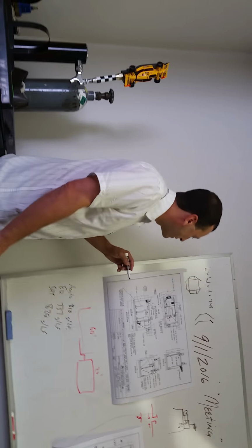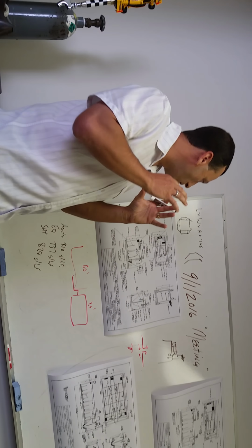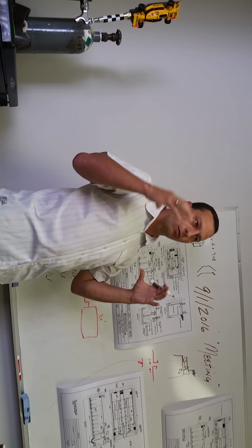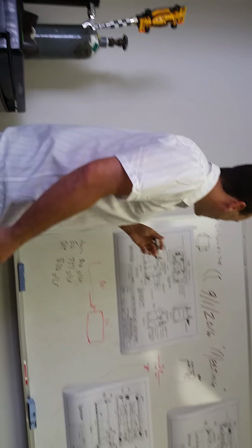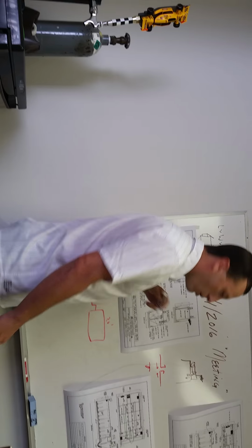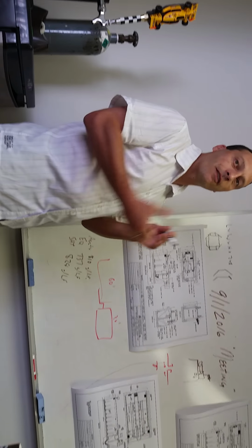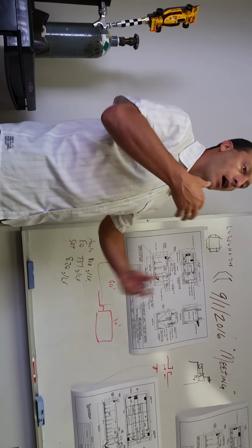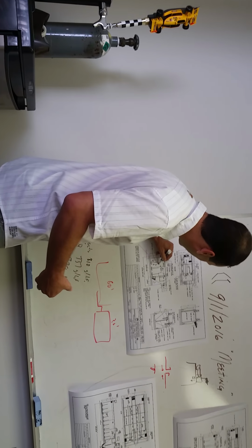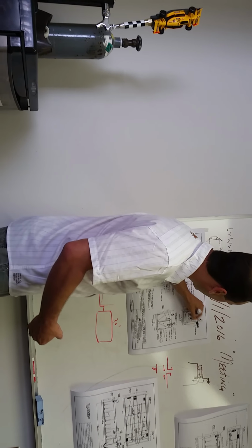The reason for the tank design, by the way, is sort of twofold. One of the strongest structural shapes is a circle, so the more circular we can keep it, the more rigid that structure is going to be from the inside and out. And also, we're trying to get this wastewater to roll. We want it moving. Once we let that air turn off and things start to settle to the bottom, once we kick it back on, we want all that stuff to get back into a mixed state. So using coarse bubbles, we get big honking bubbles coming up here, and it starts to roll, and it's going to roll off these walls.